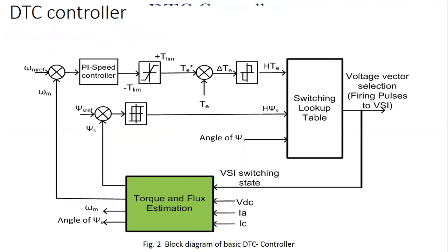For a quick review of how Direct Torque Control works: the actual speed is compared with the speed reference, and the error is given to a PI speed controller. Based on the error, a required torque command is generated — the torque at which the motor should accelerate or decelerate to reduce the error to zero. This torque command is compared with actual torque, and the error is given to a three-level hysteresis torque controller, which outputs +1 to increase torque, -1 to reduce torque, and 0 for no change.